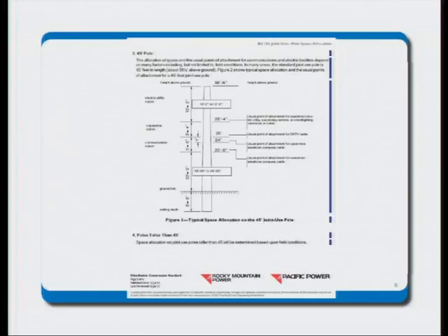One other thing, can you be on both sides of the pole? Well, both sides of the pole. They call that boxing. That's a term that's called boxing. Depending on where you are, what jurisdiction, yes. In the State of Utah, you can box. But at Rocky Mountain Power, what we'd like to see is those attachments out on a cross arm. Because if they're out on a cross arm on both sides of the pole, then a worker can still ascend and descend the pole without having to climb over. So boxing is a way of creating additional space on a pole.